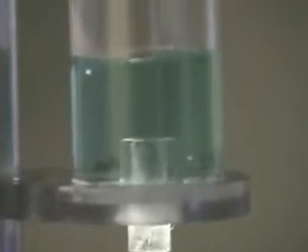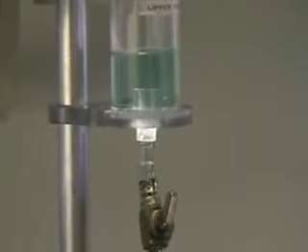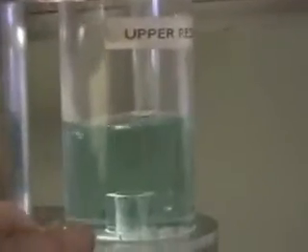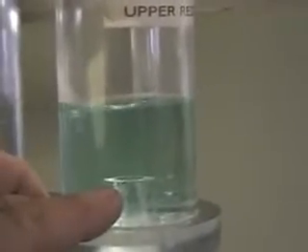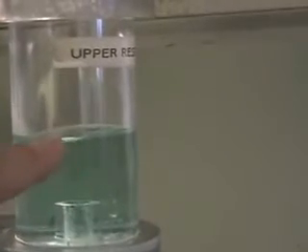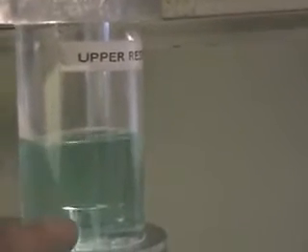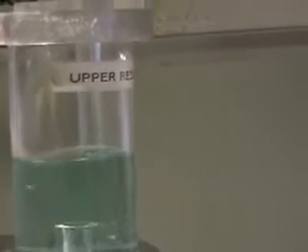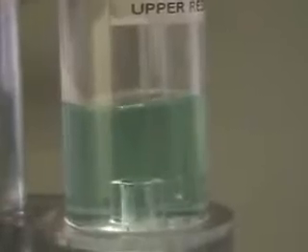Vortexes will form when there's insufficient height from the liquid surface of the tank to the intake. So in this particular case, the intake will be the bottom of the tank here, where the fluid is entering into the discharge line. And the surface, of course, is the surface that we see here. If I lower or raise that surface, we'll see definite vortex formations.